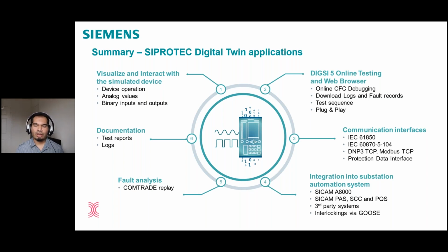Then, looking at point number 4, integration into substation automation systems. You can either integrate the actual relay in the cloud to an actual RTU, a physical RTU, which is our SICAM A8000 family, or you can report to an HMI or a SCADA system, which is a SICAM PAS or SICAM SCC or PQS.